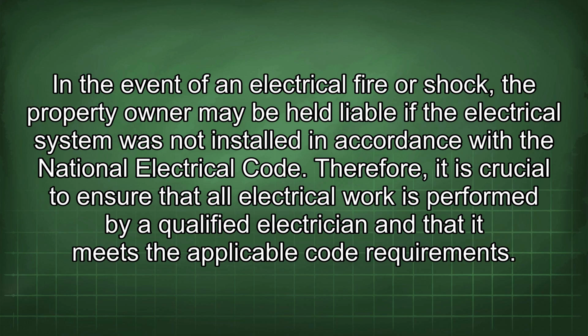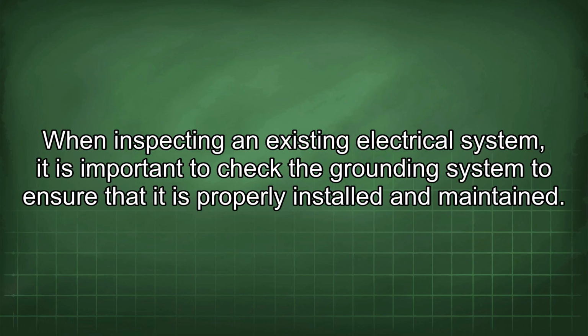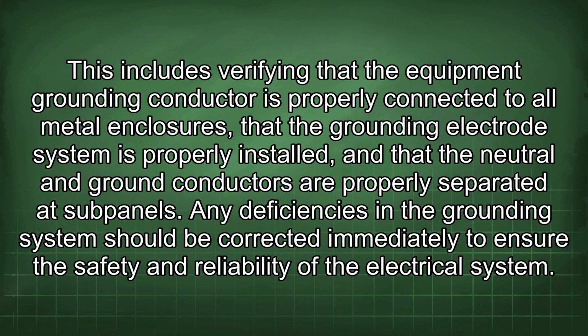When inspecting an existing electrical system, it is important to check the grounding system to ensure that it is properly installed and maintained. This includes verifying that the equipment grounding conductor is properly connected to all metal enclosures, that the grounding electrode system is properly installed, and that the neutral and ground conductors are properly separated at subpanels. Any deficiencies in the grounding system should be corrected immediately to ensure the safety and reliability of the electrical system.